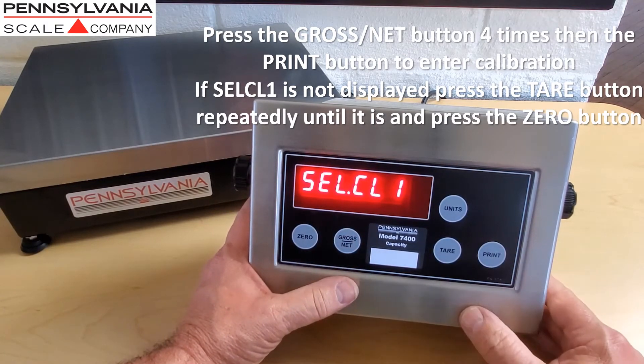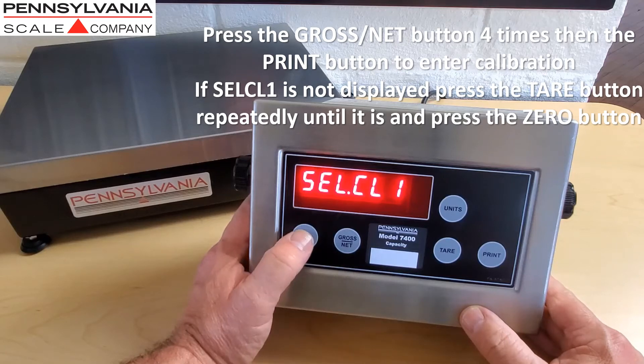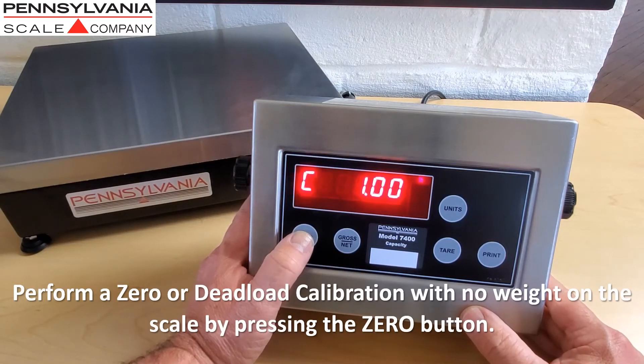If SEL CL1 does not display, press the tare button repeatedly until it does, and then press the zero button. You can perform a dead load or zero calibration with no weight on the scale by pressing the zero button.